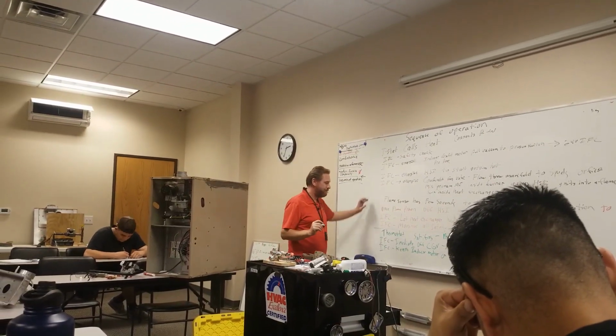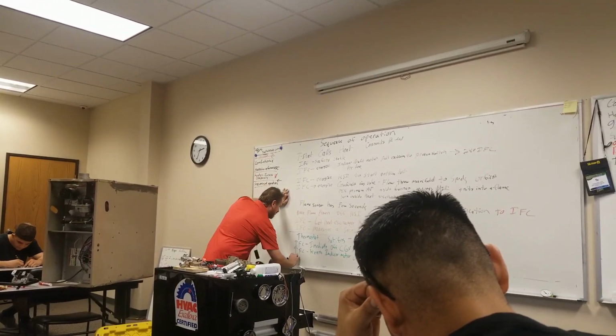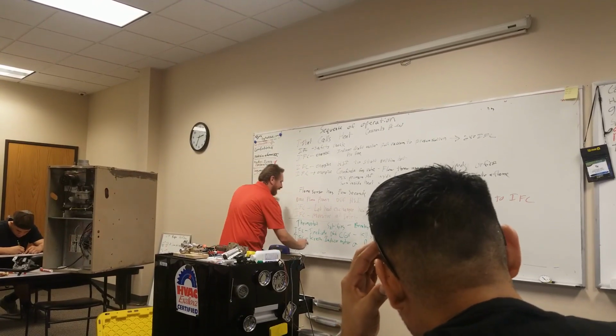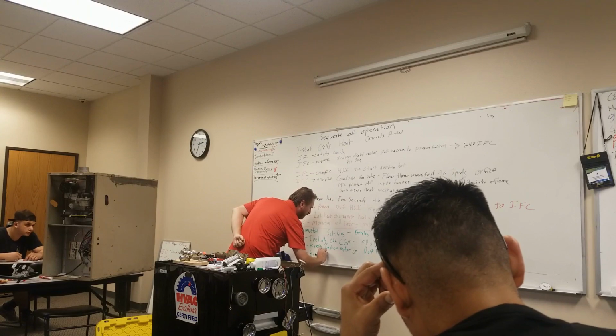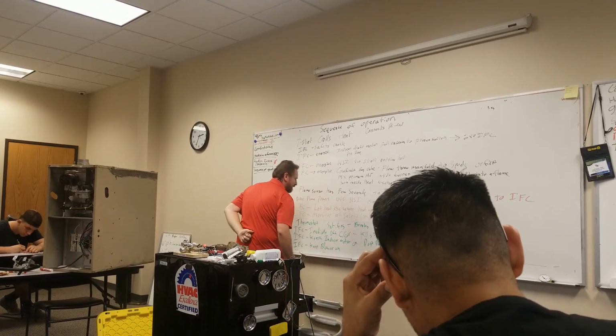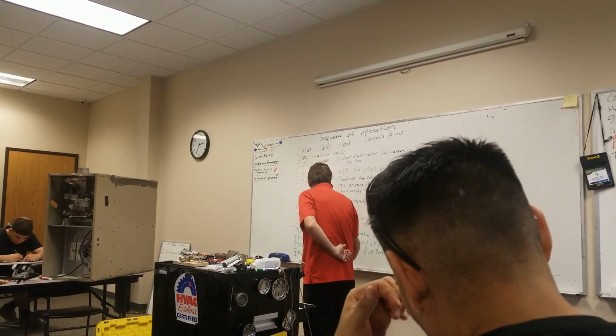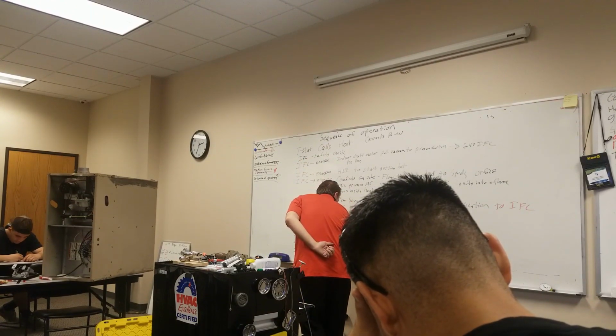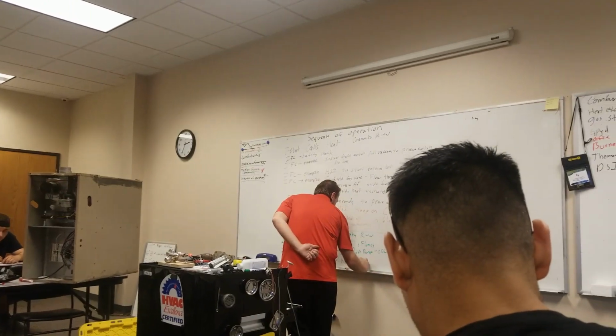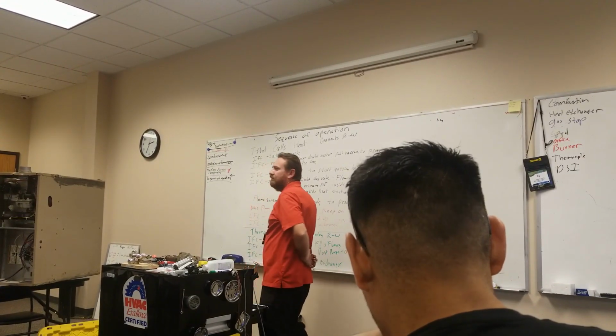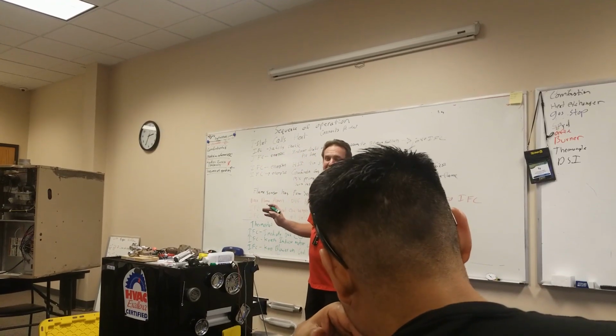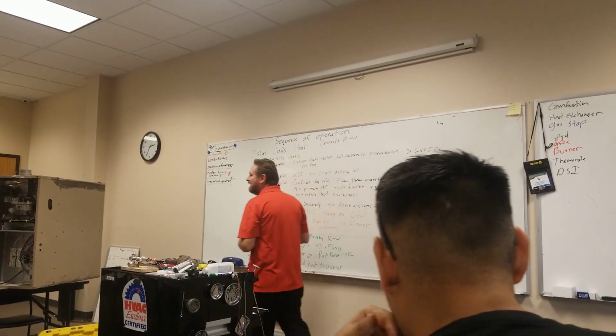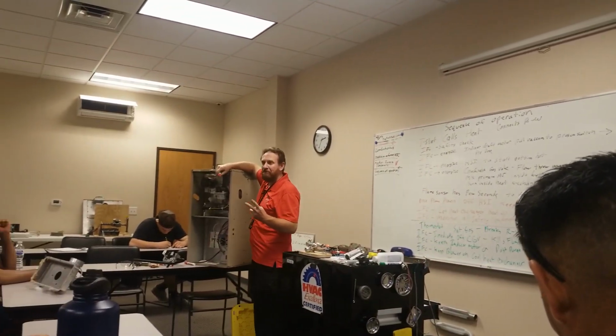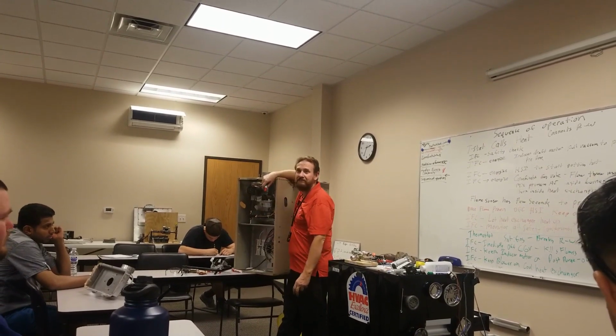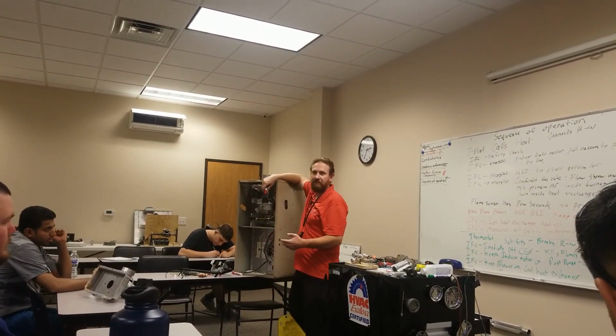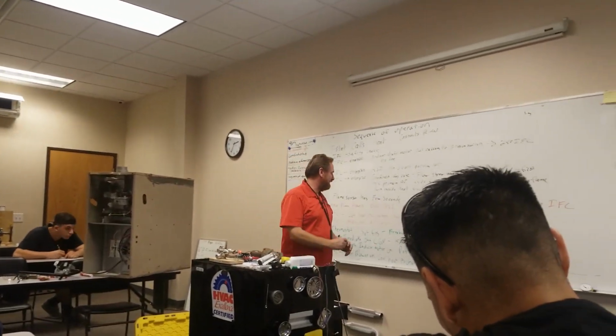All right? So far, so good? Mm-hmm. Then the IFC is going to keep the blower on to cool the heat exchanger. That heat exchanger was hot, wasn't it? Did it just have a fire inside of it? We want to keep that blower running to cool that heat exchanger down, number one. But number two, did I pay money to buy natural gas to get that heat exchanger hot? Yep. We want to put that heat into the customer's house. So there's two reasons it wants to keep it on. But cooling that heat exchanger is a big deal.